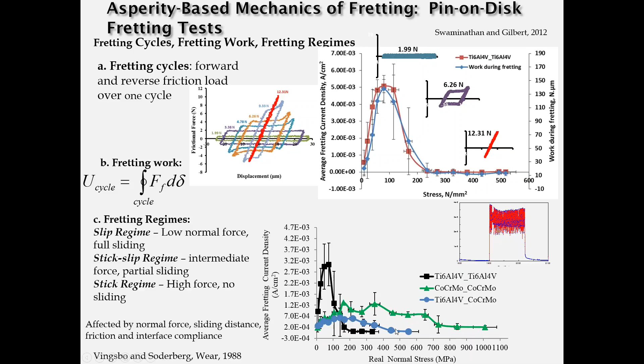This also points out that there are conditions where high contact stresses will suppress fretting and will essentially shut down the fretting corrosion reaction. Also shown in this plot are the three materials, titanium, cobalt chrome, and the mix, showing the fretting currents and their variation with the contact stress. And you can see each is very different from the other, with the mixed alloy actually giving the lowest fretting corrosion currents of the three different possibilities.